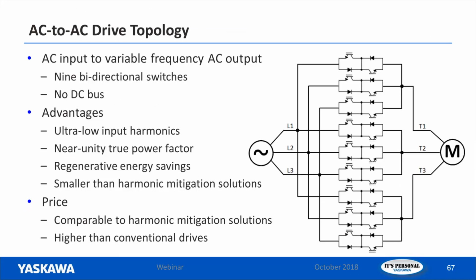The Z1000U matrix drive uses 9 of these bidirectional switches, and you'll notice there's no DC bus. If we compare this to that conventional drive topology slide I showed you several drives back, this would be the apples to apples of what the drawing would look like for a Z1000U HVAC matrix. The line voltage is coming in, hitting these bidirectional switches and being switched out to the motor. No more DC bus. So the advantages are ultra low input harmonics and a near unity true power factor, which I showed you was 0.98. We've got the regenerative energy savings, and this is also a smaller solution than other comparable harmonic mitigation solutions, like 18 pulse. The price is comparable as well, and in most cases it's going to be less costly than going with 12 pulse or 18 pulse.